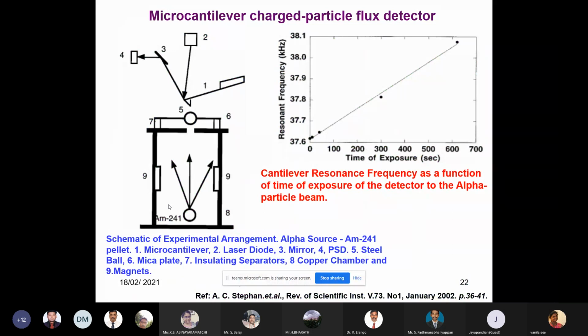Then Stephan et al. made a very small, very compact instrument for alpha flux measurement in a chamber. The chamber is isolated, maybe a steel chamber insulated with separators, a mica plate, a top mica plate. Inside they have an americium source emitting alpha particles. They are keeping it as Am-241.